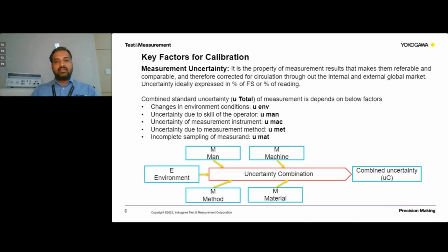So uncertainty may affect our measurement and the test results in a very significant way. That means we need to properly calculate and evaluate the uncertainties involved in the measurement. Only then will we be able to identify what accuracy or what uncertainty the master instrument should have for the calibration. That entire thing will be defined by proper evaluation of the measurement uncertainty, or combined uncertainty.